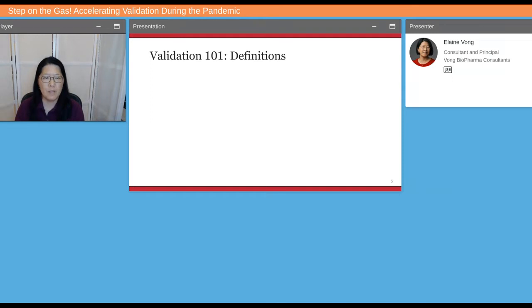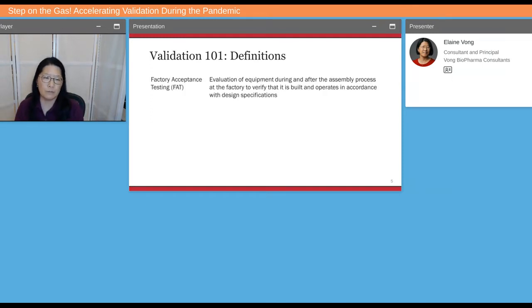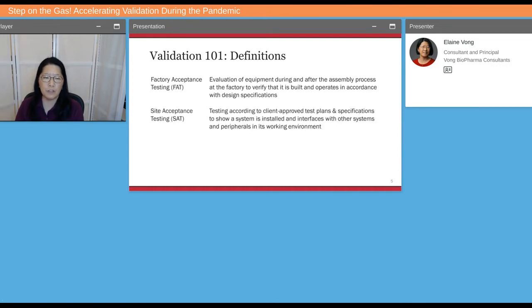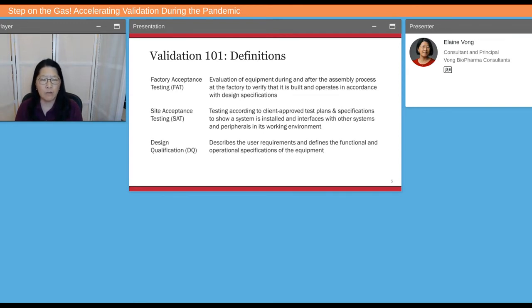So Validation 101 definitions. Factory acceptance testing is evaluation of equipment during and after the assembly process at the manufacturer to verify that it is built and operates in accordance with design specifications. Site acceptance testing is testing according to client-approved test plans and test specifications to show a system is installed and interfaces with other systems and peripherals in its working environment. And design qualification describes the user requirements and defines the functional and operational specifications of this equipment.